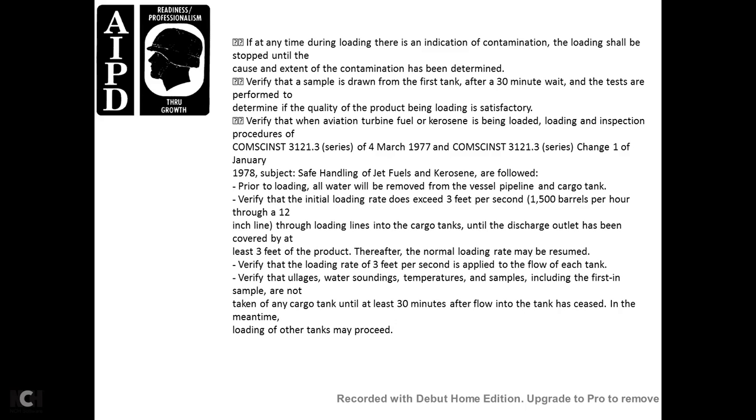If at any time during the loading there is an indication of contamination, loading should be stopped and the cause and extent of the contamination determined. Verify the samples drawn for the first tank, allow a 30-minute wait, and when the tests are performed, determine if the quality of the product being loaded is satisfactory.